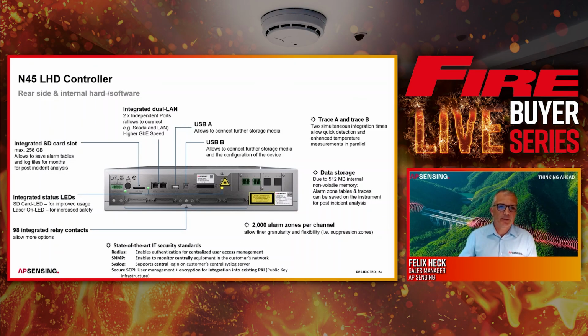On the backside of the controller, I don't want to go into every detail here, but to summarize, of course, we have interfaces with Modbus, TCP/IP. We can provide information through the LAN ports. We have the relays here. We have the 10 standard relays, but we can provide extensions, 44 or 88 relays. So in total, 98 relays are possible at the backside of the controller. We have the sensor channels here on the right side. We have controllers with just one sensor channel, with 2 sensor channels, or here fully equipped with 4 sensor channels.